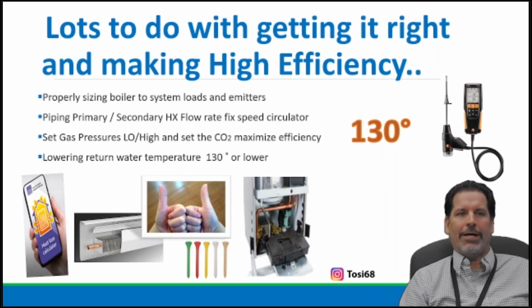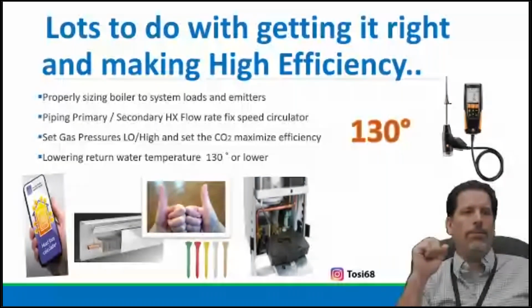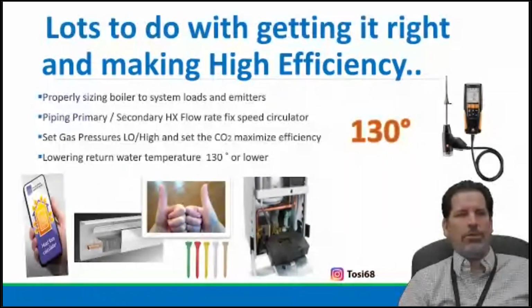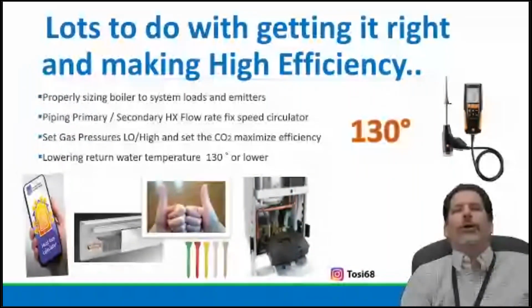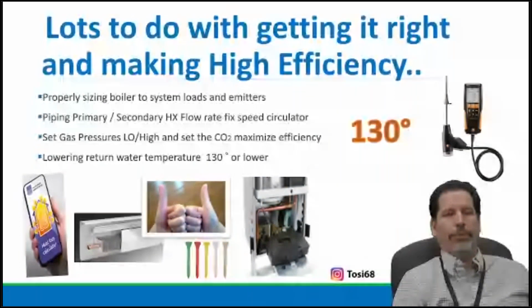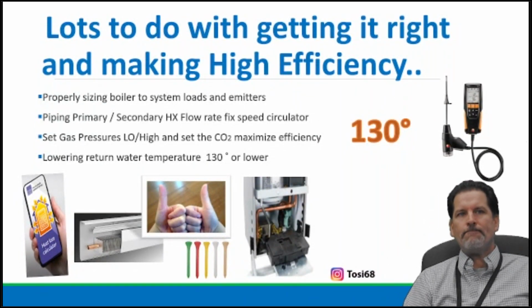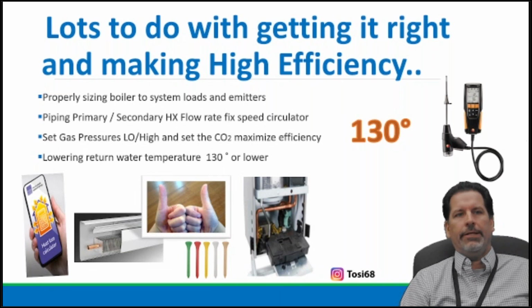But control strategy knows when it's a domestic call versus a heating call. And that's why the outdoor sensor's there and other things of that nature. So I know I can set the water temperature for my heating versus my domestic. Domestic becomes priority, high fire, go, go, go, 400, 600 BTUs, 300 gallons of storage waiting for somebody to wash their hands. It gets to be some kind of craziness like that, but that's reality where we live, right? So getting comfortable with just lowering water temperature is that stepping off point.